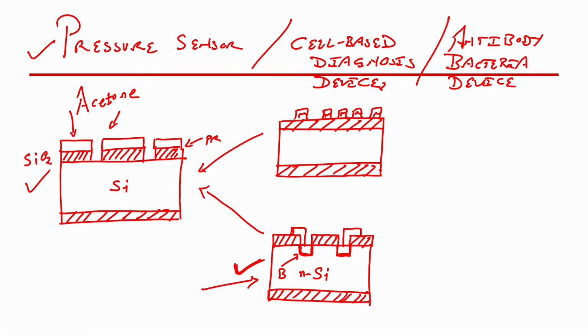Now, this is another way of doing it. Like I said, we are taking a contact from this piezoresistive material, right. But in both the cases, now if you apply a pressure like this and similarly on this, then you will not find a great change in the piezoresistive material, because your silicon is a hard material, and that is why what you have to do in both the cases, you have to create a diaphragm.